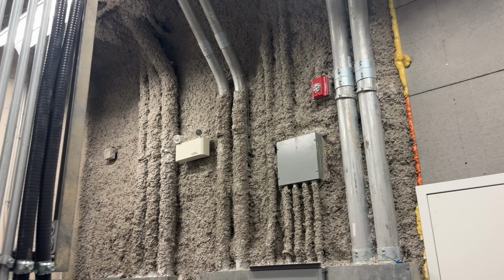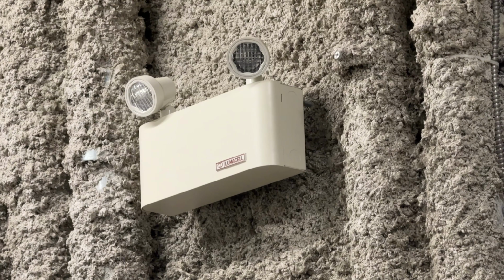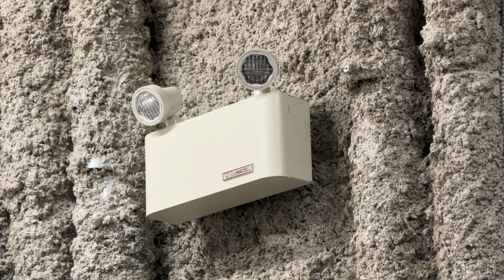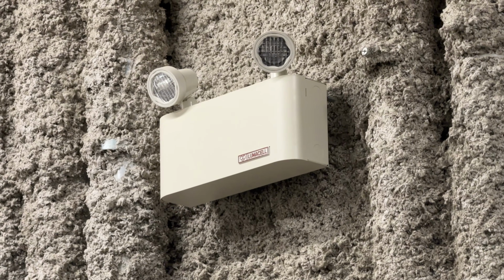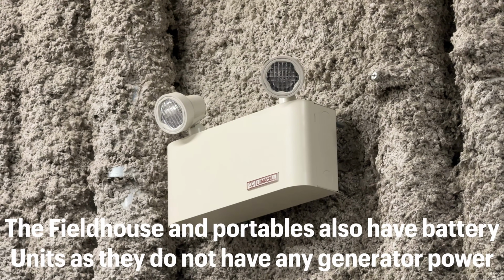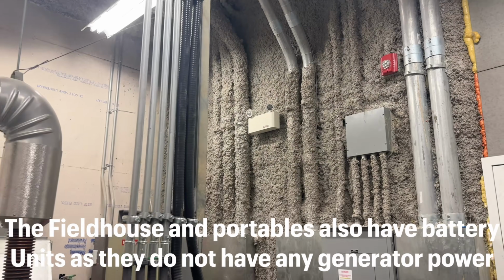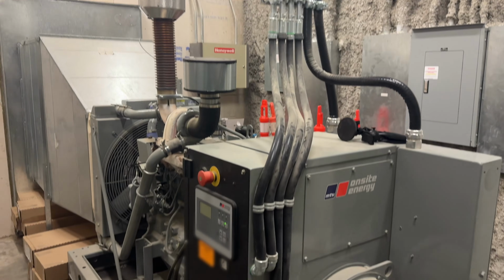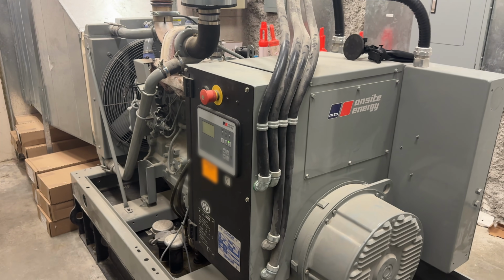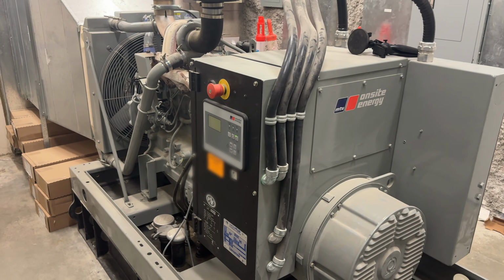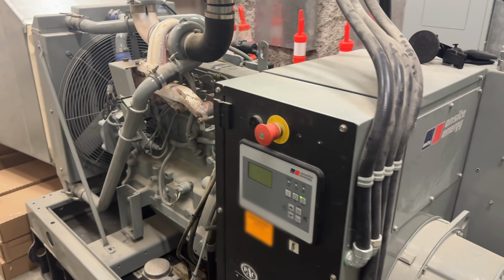Because this school has a generator, we do not have battery backup emergency lighting like you would see in many buildings, except for 2 units. There's one in the generator room and one in the electrical room. Those are required to be in the electrical room and generator room in case something goes wrong with the generator, to provide light for manual operation of the unit.